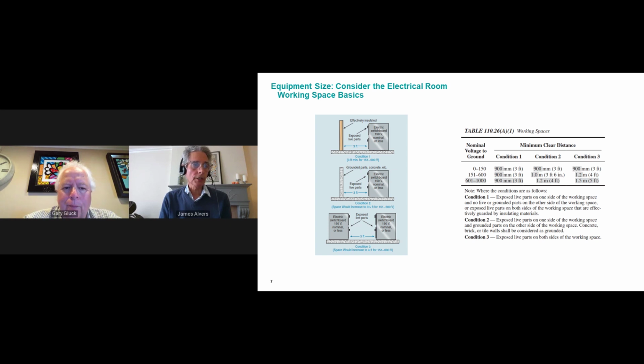For switchboards over 800 amps, you will need personnel doors with listed panic hardware that open outward to facilitate egress. One door is required for anything under 1200 amps. If you go over 1200 amps, or the switchboard is 6 feet wide, you need 2 doors unless you have double the working space in front and a clear path out. I don't show that drawing on this particular slide, but once again, it's all in section 110.